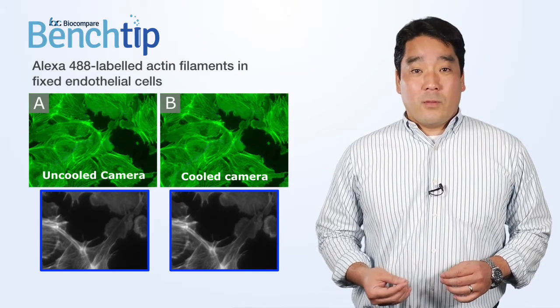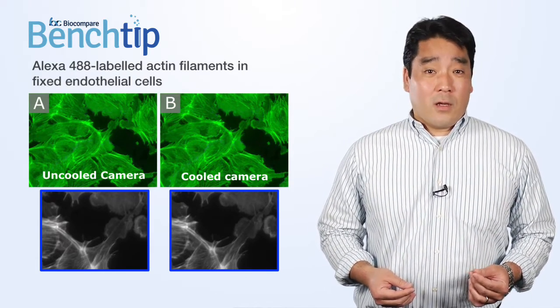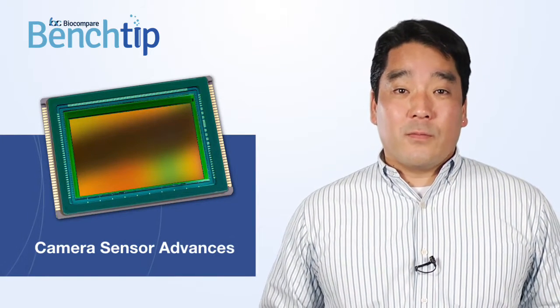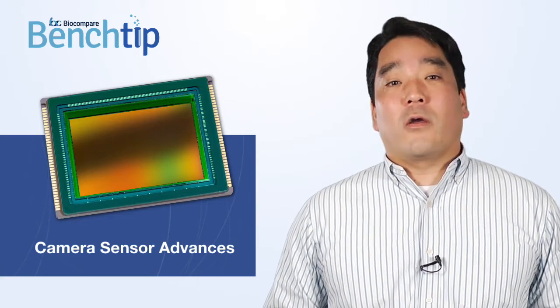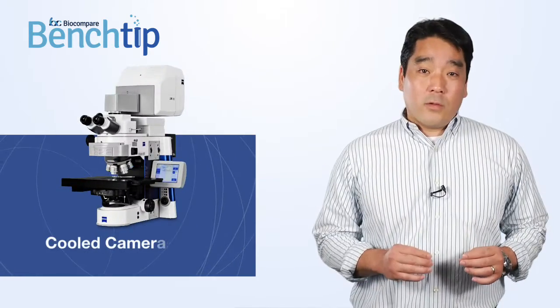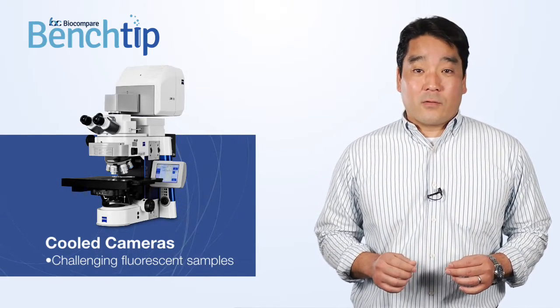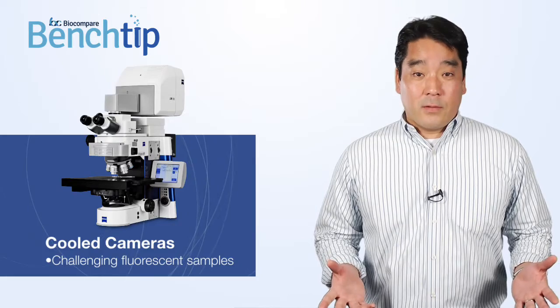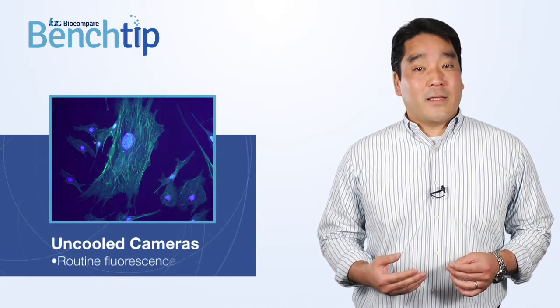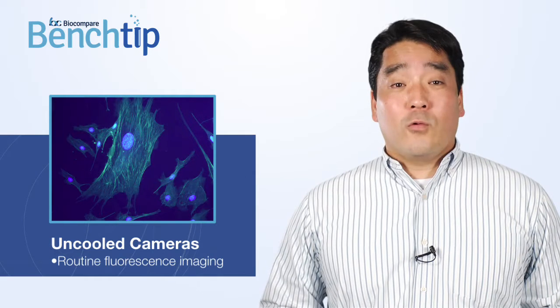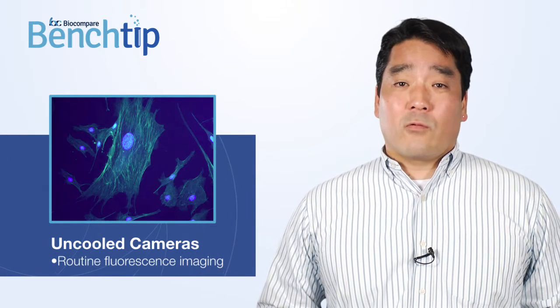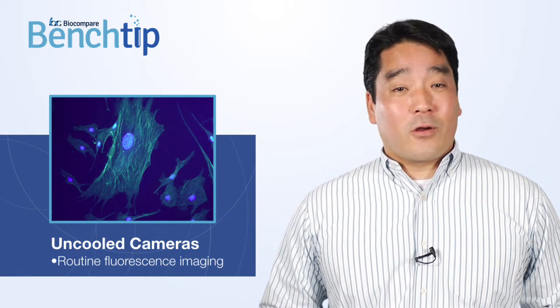The main difference between the two images is that the one on the left is taken with an uncooled camera and the one on the right is from a cooled camera. Historically, cooling was necessary for fluorescence imaging. However, advances in camera sensor technology over the last 25 years mean that cooling is no longer required for routine fluorescence imaging. Cooled cameras are ideal for challenging fluorescence samples that require more sophisticated microscopes such as confocal microscopes. For most fluorescence imaging situations, cooling is not required. Uncooled cameras can provide excellent, low-noise images for general fluorescence applications at a lower cost than a cooled camera.